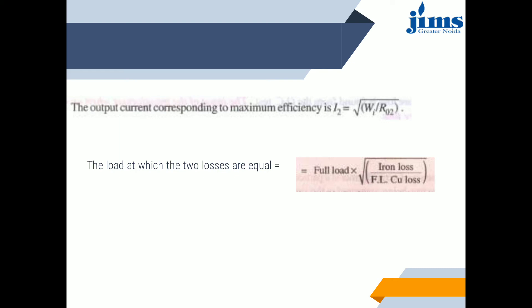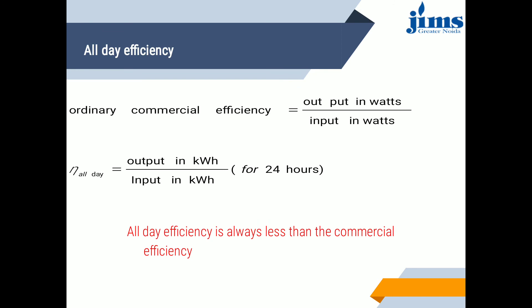It is important to note that since copper loss depends on current and iron loss depends on voltage, the total loss in the transformer depends on voltage and current and is independent of the load power factor. The transformer is therefore rated in KVA, not in KW. Ordinary commercial efficiency = output in watts / input in watts. All-day efficiency = output in KWh for 24 hours / input in KWh for 24 hours. All-day efficiency is always less than commercial efficiency.